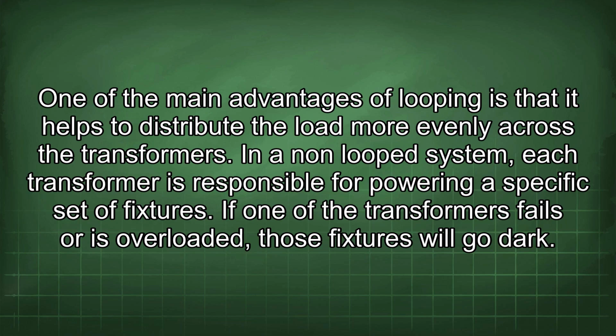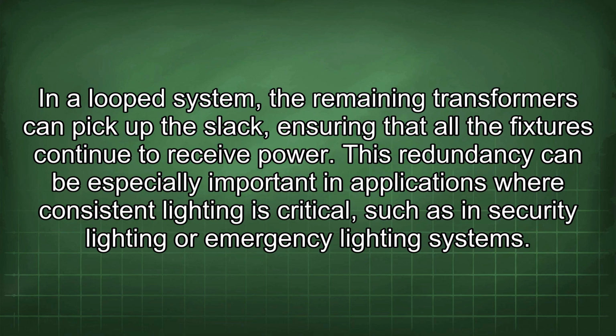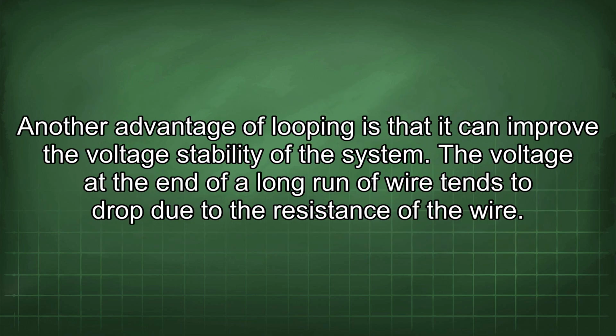One of the main advantages of looping is that it helps to distribute the load more evenly across the transformers. In a non-loop system, each transformer is responsible for powering a specific set of fixtures. If one of the transformers fails or is overloaded, those fixtures will go dark. In a loop system, the remaining transformers can pick up the slack, ensuring that all the fixtures continue to receive power. This redundancy can be especially important in applications where consistent lighting is critical, such as in security lighting or emergency lighting systems.